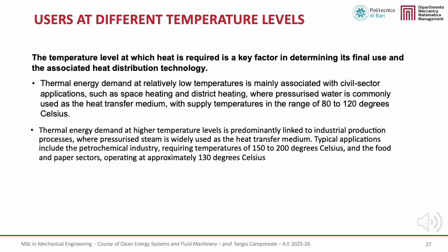In this slide, we highlight that the type of user and the final application determine the temperature level at which heat is required and therefore the appropriate heat distribution technology. Different categories of users are characterized by different thermal needs, which translate into specific temperature levels and heat transfer media. In the civil sector, where heat is mainly used for space heating and district heating, thermal demand is typically at relatively low temperatures. In these applications, pressurized water is commonly used as the heat transfer medium, with supply temperatures generally between 80 and 120 degrees Celsius.